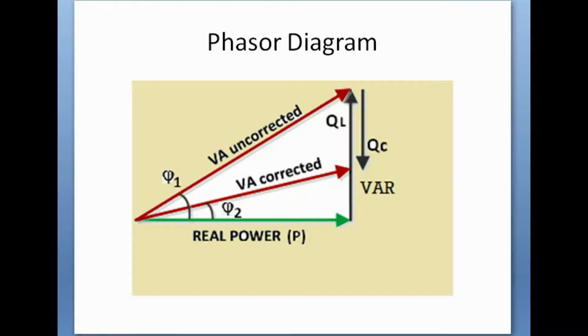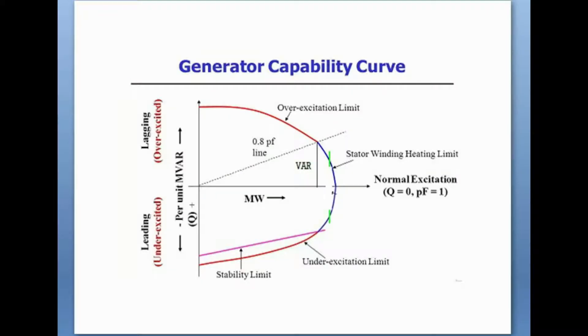Now after power factor correction, Phi 2 is the power angle between voltage and current. Cos Phi 2 is the corrected power factor. Because of this correction, we can see from this phasor diagram that the KVA demand is now reduced, as well as the reactive power requirement is also reduced.